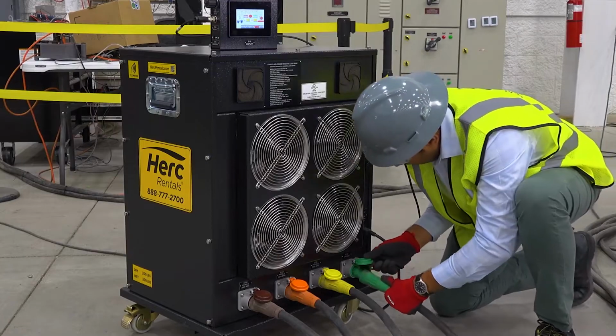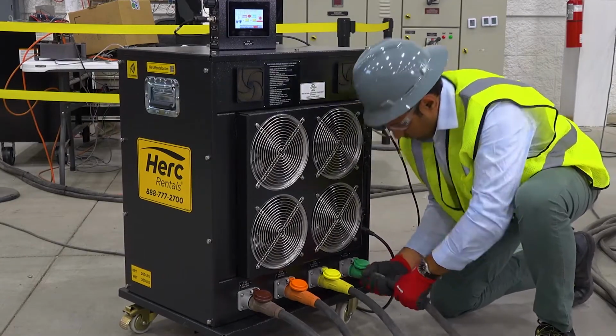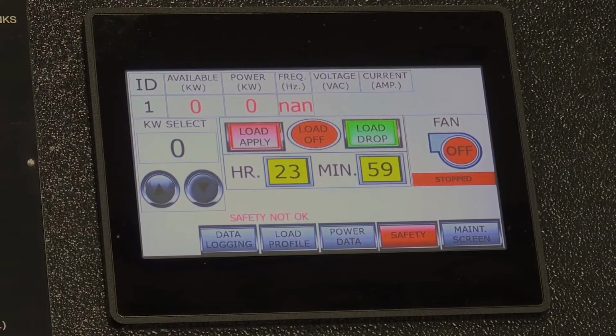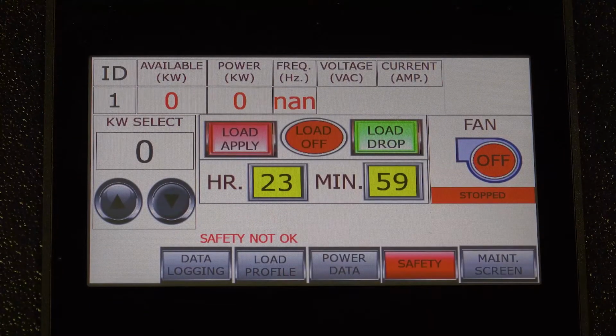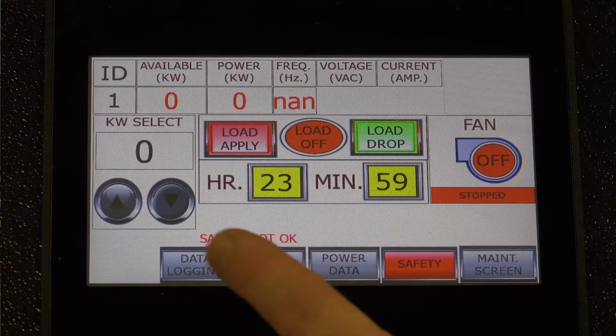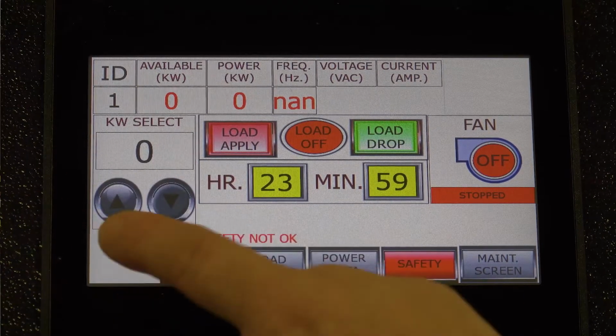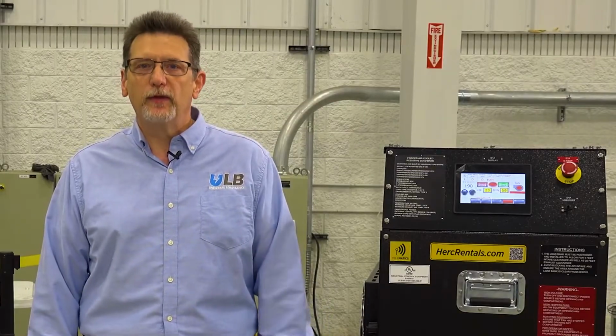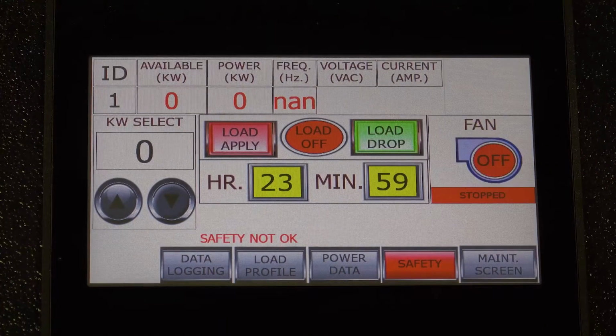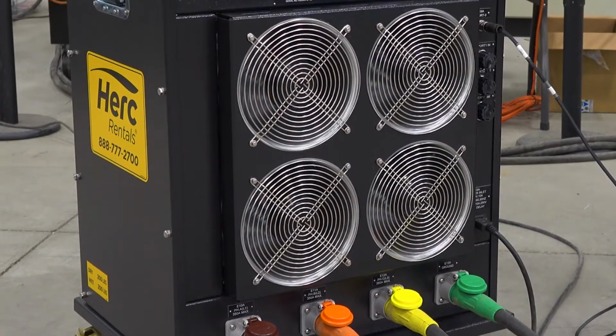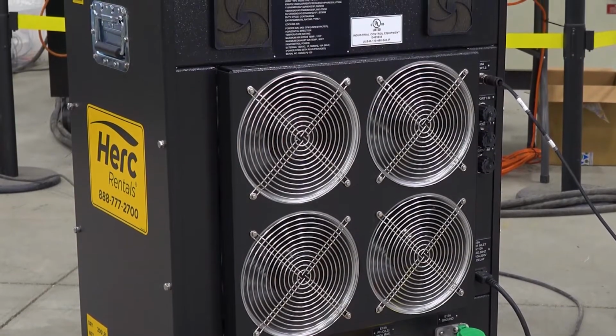Once the unit is placed properly and input voltage is applied, the user can start the loading process via the color touchscreen HMI. During operation, it is always best to start with the smaller load steps and slowly add load until the power source is at its full output. When finished operating the load bank, simply drop the load and the unit will automatically go into a 5-minute cooldown period. After 5 minutes, the unit will automatically shut off.